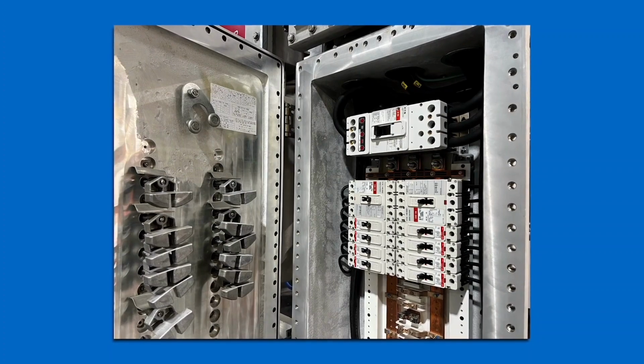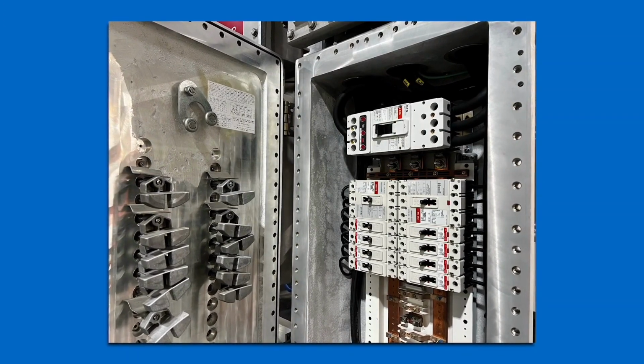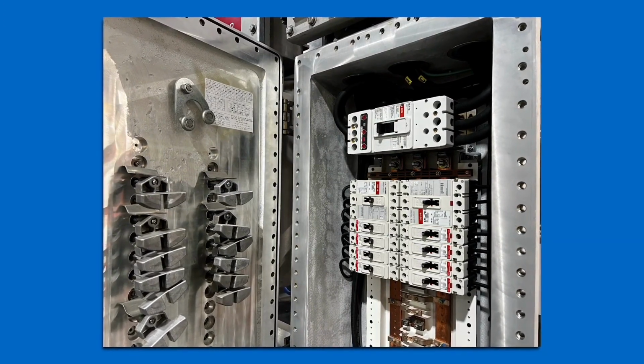A fuel is any flammable substance that can ignite and continue to burn. The second component is an oxidizer. Often, ambient air, which is about 20% oxygen, will be enough of a reactant, and the last element needed to start a fire is an ignition source. Electricity is a prime source of ignition because equipment, such as switches and motor starters, can produce arcs or sparks in normal operation. Other hazards are devices that produce heat, such as luminaires and motors. Here, service temperatures may exceed the safe limits of many flammable atmospheres.